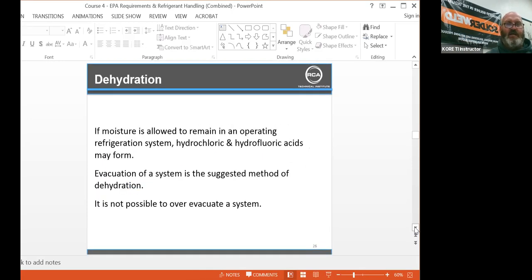If moisture is allowed to remain in an operating system, hydrochloric and hydrofluoric acids may form. Evacuation of the system is a suggested method of dehydration. It is not possible to over-evacuate a system. We all know that. You can double, triple evacuate. We're seeing micron levels in the hundreds, so it can never be too low.